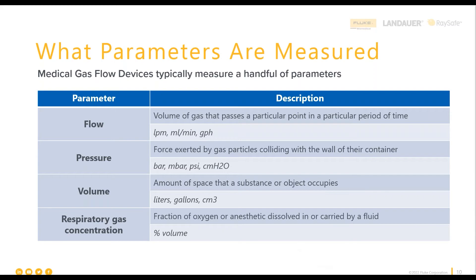There are four main functions of medical gas equipment — four main parameters. They measure flow, pressure, volume, and concentration. I want to go into a bit of detail on each so we fully understand what they mean and how they're measured.